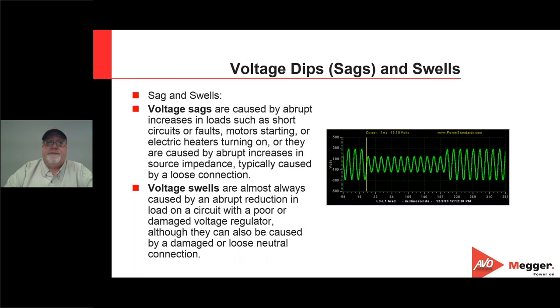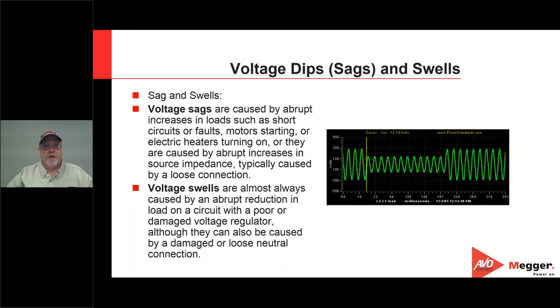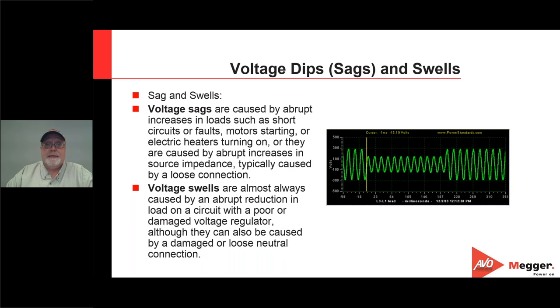Voltage SAGs are typically caused by large loads turning on. When a large load such as a motor turns on, you'll get a large inrush of current that produces a momentary SAG in the voltage. These happen on a daily basis. SAGs can also be caused by poor connections as well as source faults — if you have a single line-to-ground fault, we can see a SAG until the protective devices kick in.